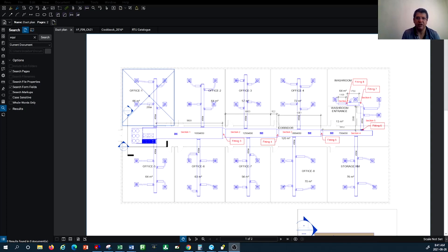Why do we have to do the static pressure calculation? Because when you size your rooftop unit or whatever air distribution unit — and specifically its fan motor — you have to understand what the maximum static pressure is that the fan motor can overcome to deliver the volume of air to the space.